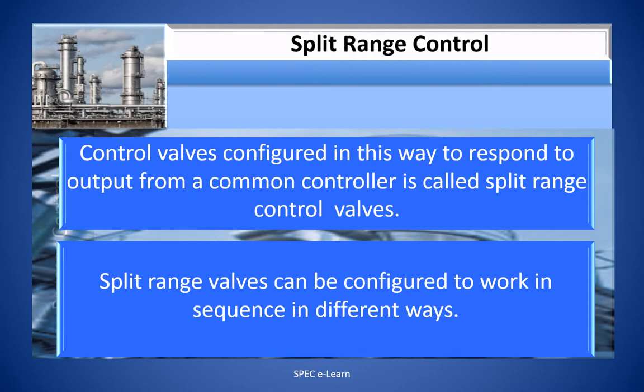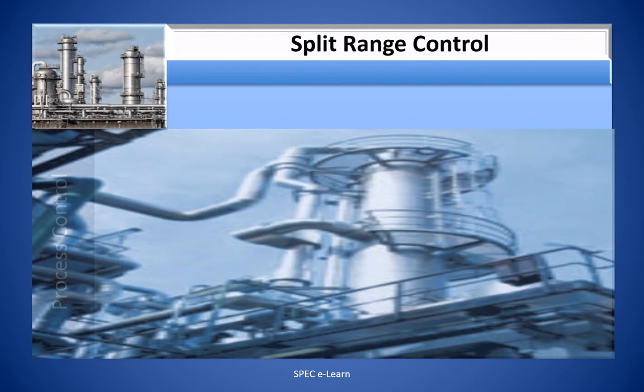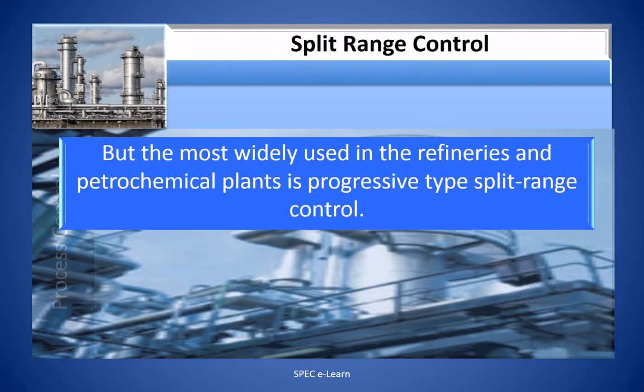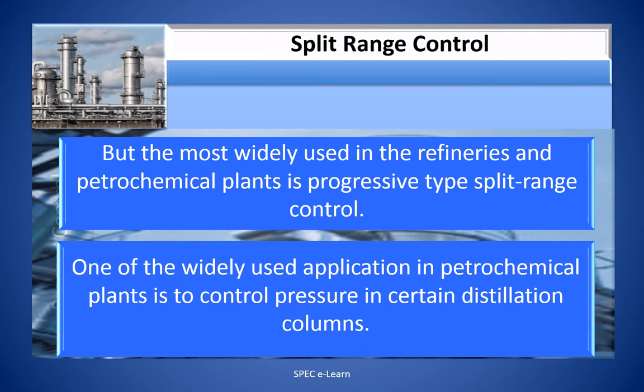Split Range Valves can be configured to work in sequence in different ways, but the most widely used in refineries and petrochemical plants is Progressive Type Split Range Control. One of the widely used applications is to control pressure in certain distillation columns.